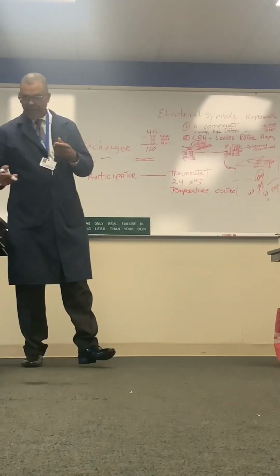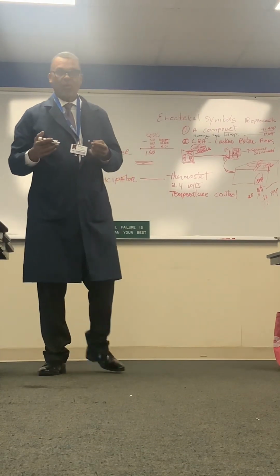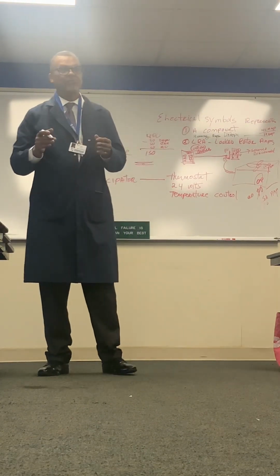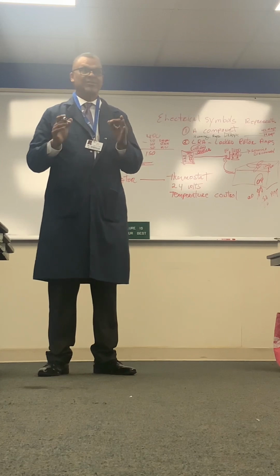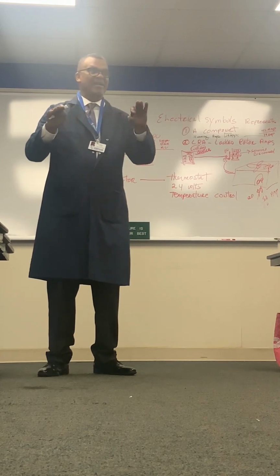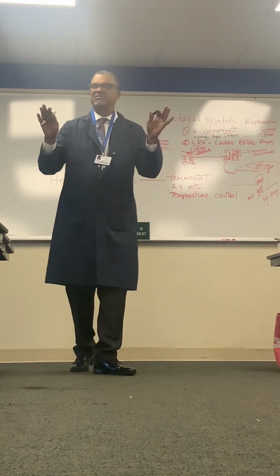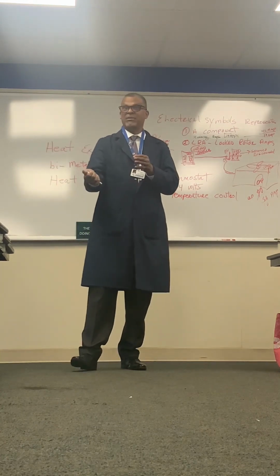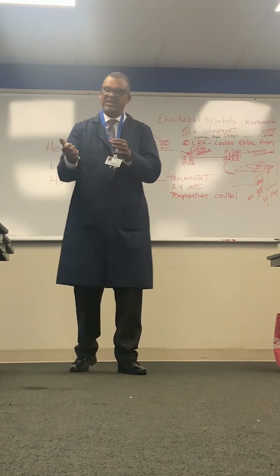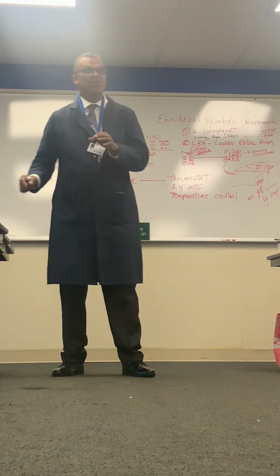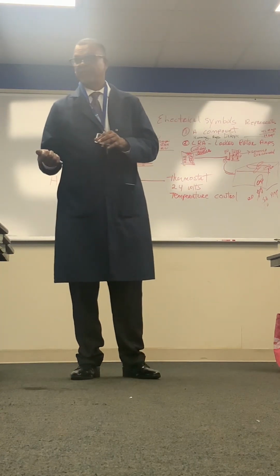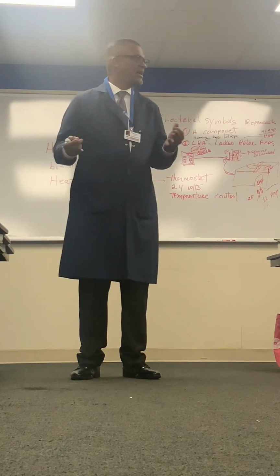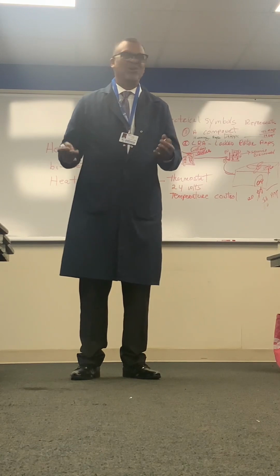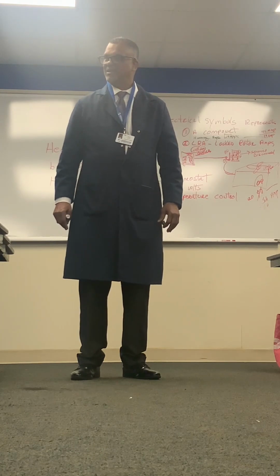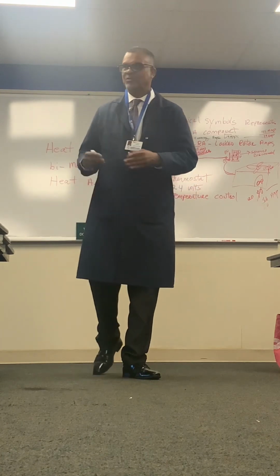When you see a breaker or a component that's marked for running amps, that's all it needs to be balanced and to continuously run. That's why we amp out. You have an amp meter and you say, hey, that's amps. But you look at that rating as a service person and say, hey, that thing is at 36 amps. And you might say, I wonder why it keeps going off.